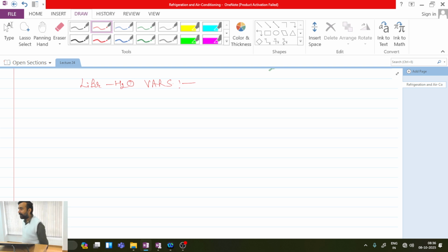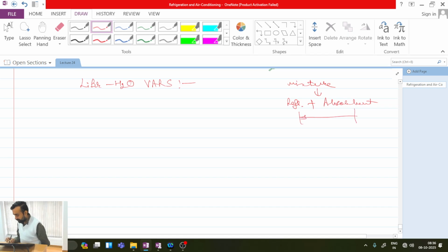So if we have some combination where the solution is a mixture made up of the combination of refrigerant plus absorber, made up of substances whose boiling temperature difference is very high, greater than 200 Kelvin, then you can achieve 100% separation and you need not go for this additional arrangement in the generator itself, nor for the additional dephlegmator, analyzer and exhausting column, etc. Okay, so these additional components are not needed. It means the system configuration will be simple.